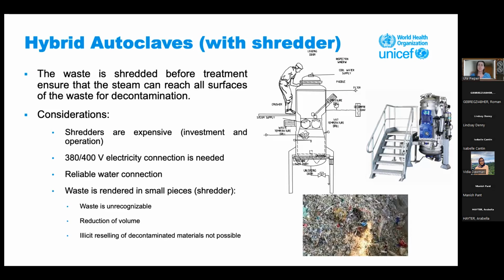Another possibility is also, again, an autoclave, but in this example, we see an autoclave with an integrated shredder. That means that the waste is getting into the system, it is shredded, so rendered into small pieces, and then it is autoclaved. In these systems, we do not necessarily need a vacuum system because the waste is already put into small pieces and the steam can easily get to the surfaces of the waste. So there are advantages.